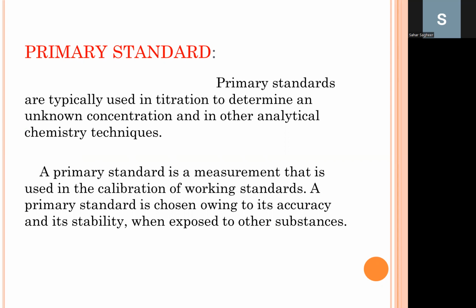Primary standard in metrology is a standard that is sufficiently accurate such that it is not calibrated by or subordinate to other standards. Primary standards are defined via other quantities like length, mass, and time. Primary standards are used to calibrate other standards referred to as working standards.